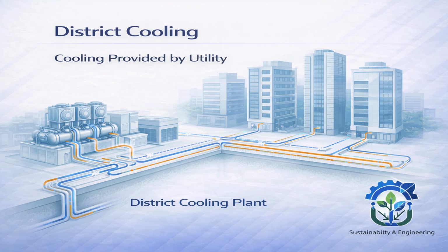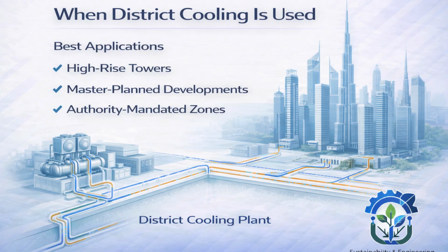Now let's understand what this means for the building designer. From a designer's perspective, district cooling simplifies HVAC plant rooms, reduces space requirements, and removes major maintenance responsibility. However, there is an important shift. The building owner is now dependent on the utility, is subjected to cooling tariffs, and is bound by the utility design requirements. So while plant complexity reduces, commercial and coordination complexity increases.